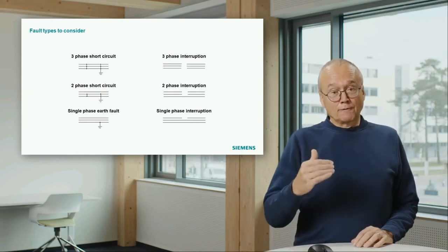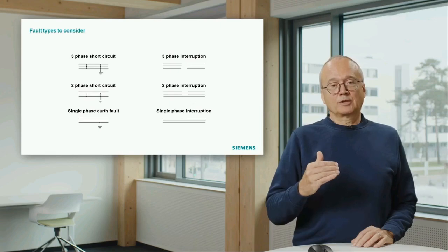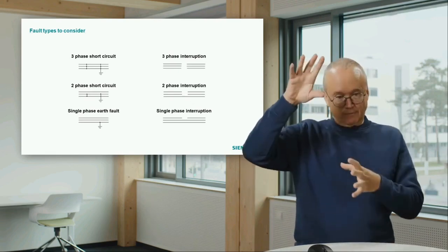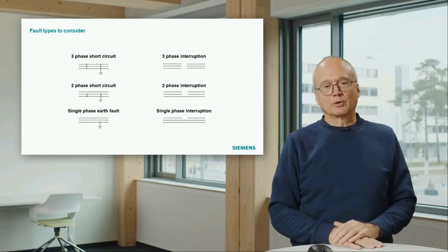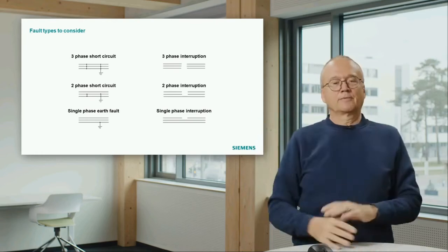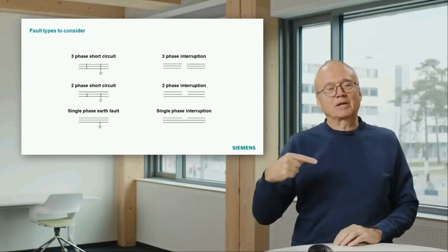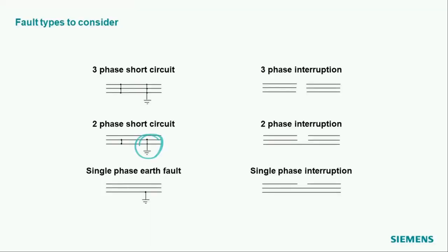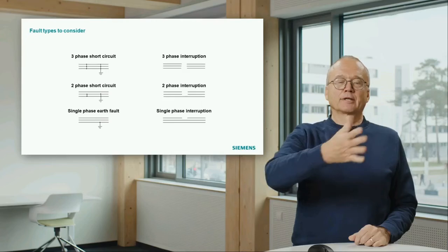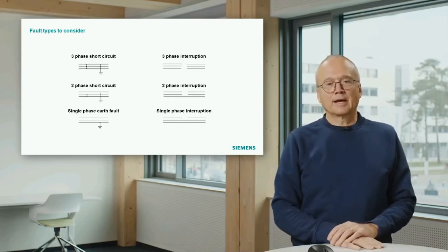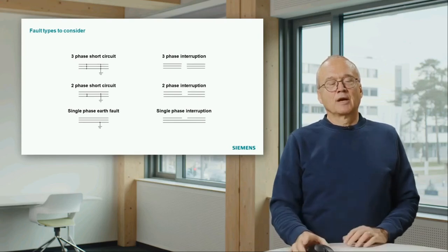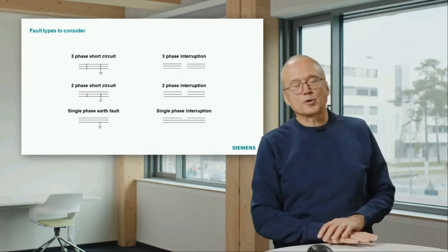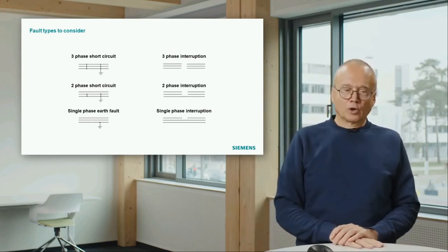Sometimes they evolve to a phase to phase to ground fault. That means if you have on one tower a lightning arc burning, a short circuit burning on the tower, there's a lot of hot air flowing around there, and that sometimes affects also another phase. Then you get this two-phase to ground fault. And of course, you can also have just a short circuit between two phases, for instance, if the conductors of an overhead line start some oscillations. And of course, there is also a risk of a three-phase short circuit. That is not very often.